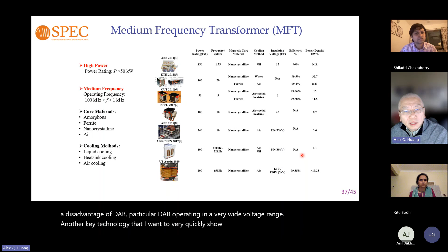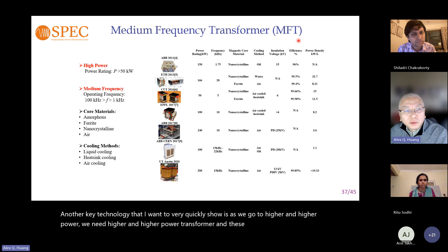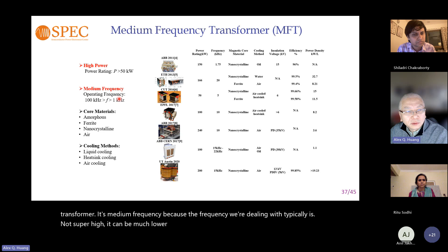Another key technology that I want to show very quickly is that as we go to higher and higher power, we need a higher and higher power transformer. These are called medium frequency transformers. It's medium frequency because the frequency we're dealing with is typically not super high, it can be much lower than 100 kilohertz. So basically from 100 kilohertz to about 1 kilohertz range.